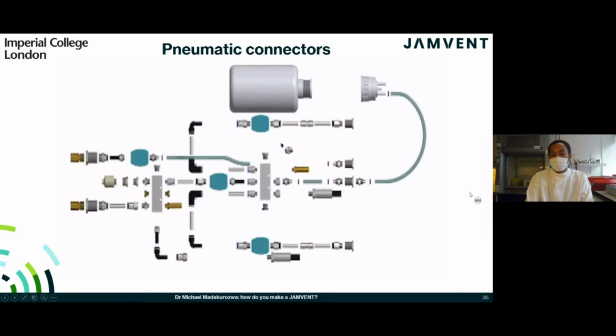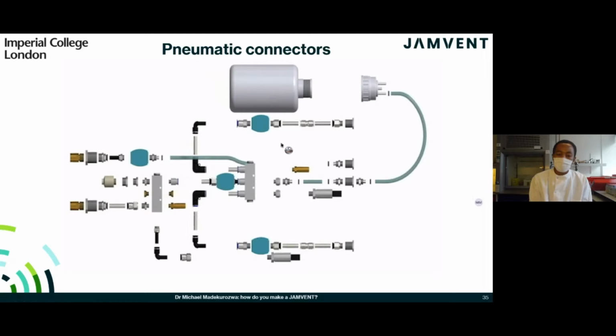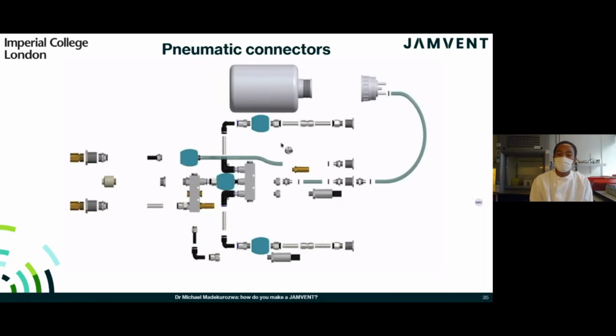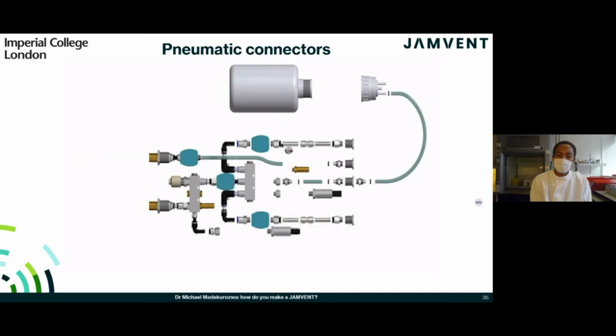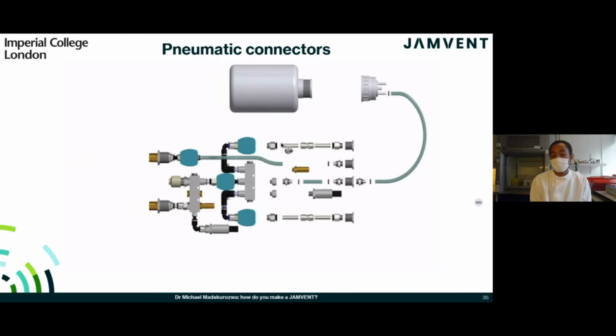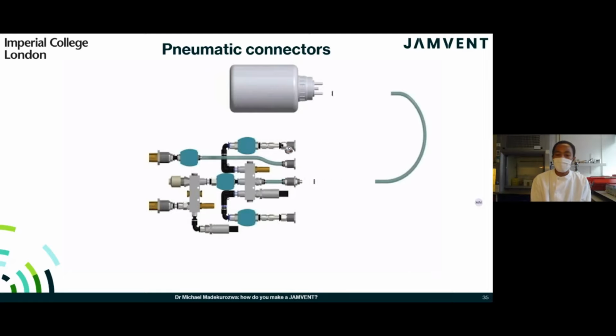And the process repeats. The pneumatics of the system are built up of push connectors and threaded connectors. The reason why we built the entire pneumatics out of push connectors and threaded connectors is because these are easy to source, easy to connect, easy to disconnect, and so easy to clean. Typically, systems are built out of custom-built pneumatics. The problem with custom-built pneumatics or custom-built manifolds is they're difficult to produce at scale, and they tend to be quite expensive.